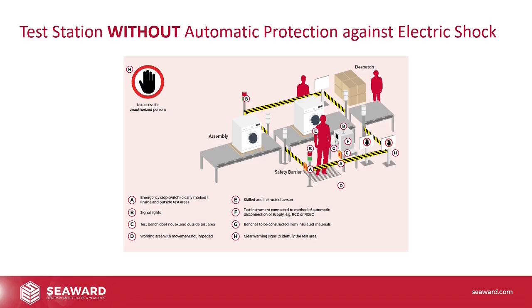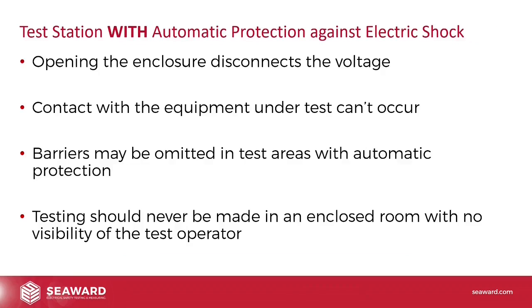And the benches are constructed from insulating materials, so that conveyor could be a plastic conveyor, something like that. And clear warning signs are there to identify the test area and warn other non-trained personnel not to enter. For a test station with automatic protection, the theory here is that the equipment is tested inside an enclosure, so something made out of plastic or wood or something that is isolated. So opening the enclosure will disconnect the voltage. Opening the enclosure stops the testing, which means contact with the equipment under test can't occur during the test.